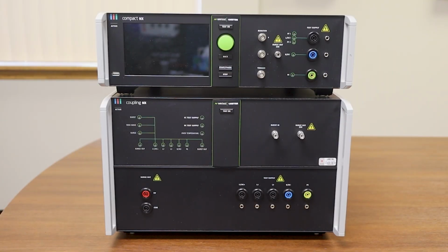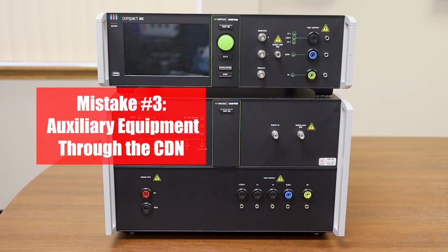Another mistake we see is when auxiliary equipment electrically connected to the equipment under test is not connected through the coupling-decoupling network. This can cause lab circuit breakers to be tripped or unintended interference on the mains connection.